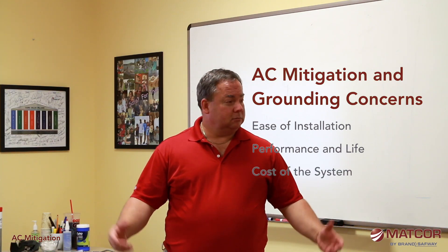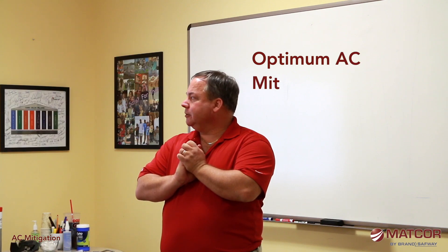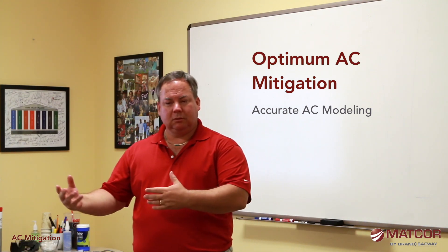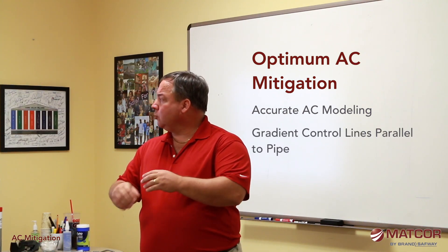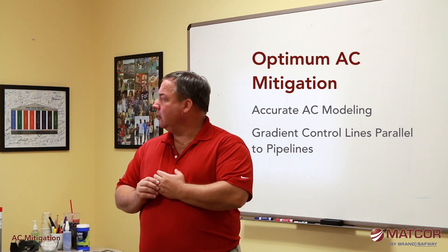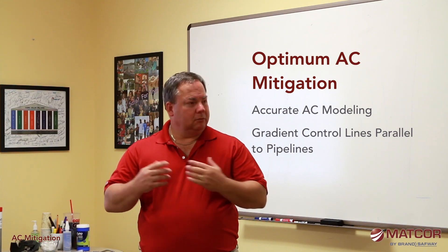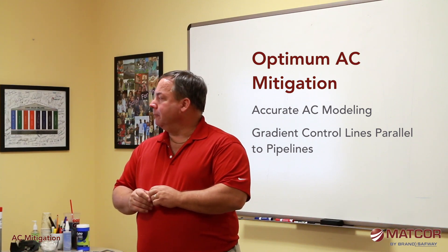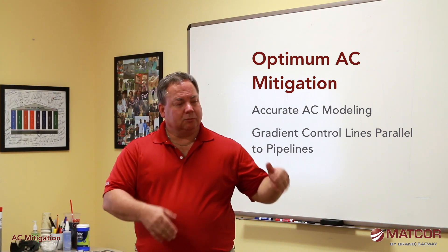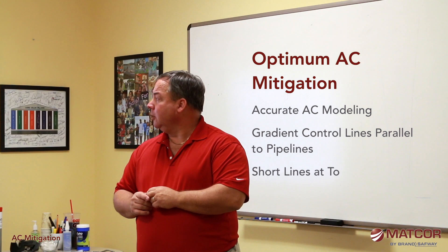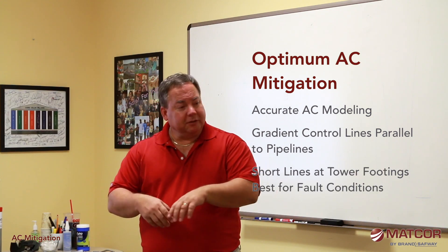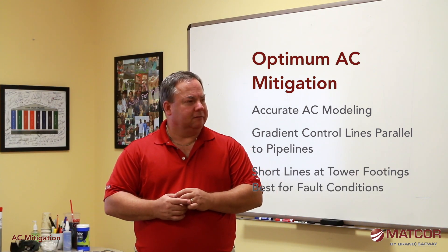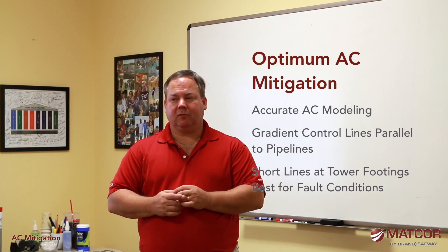Optimum AC mitigation modeling is only as good as the model, so it's really important that the AC mitigation modeling we do is accurate. Gradient control lines parallel to the pipeline are probably the most common grounding system being used right now, although there are quite a few locations using deep anode systems as well. For fault conditions, short lines at the tower footings tend to be an effective mitigation strategy.